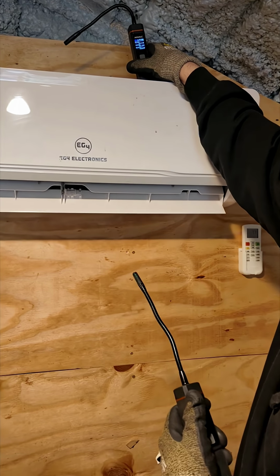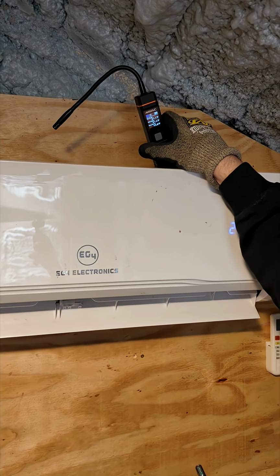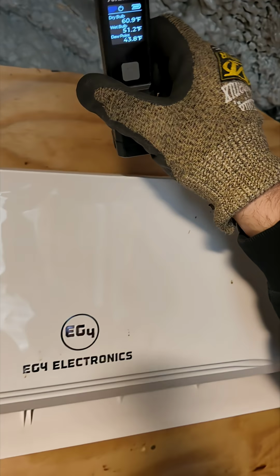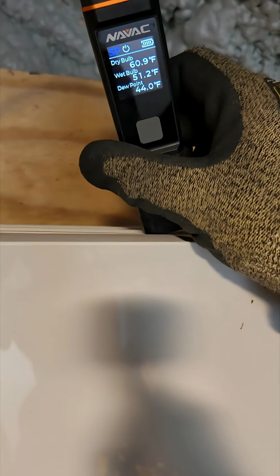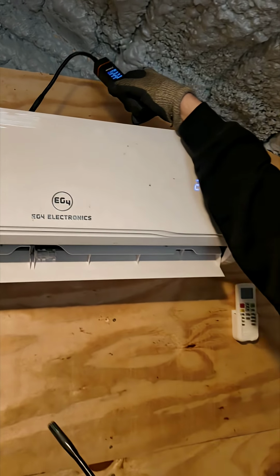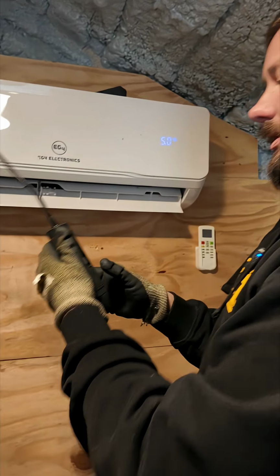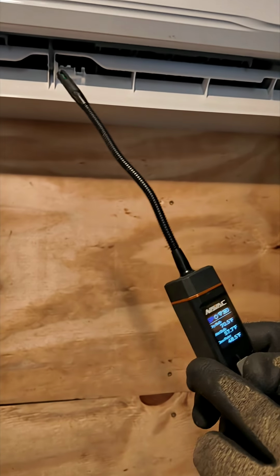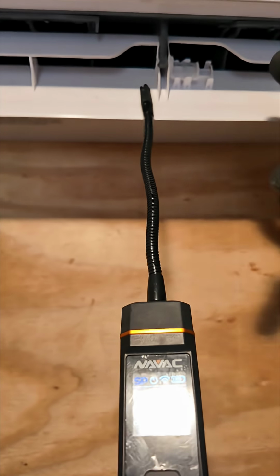The unit is in the heating mode. I'm checking the return air temperature, which it looks like it's 61 degrees. See that? 60 degrees right there. And this is where we're pulling in the air, so that's the return air.